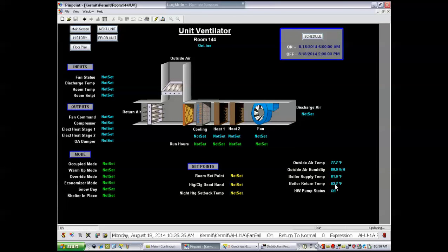These values on this side are coming from a different controller. That one's coming from boiler A, outside air temperature. That one's coming from boiler A controller, outside air humidity. Boiler B, hot water supply temperature. That's how you know what point whatever value you're looking at comes from.